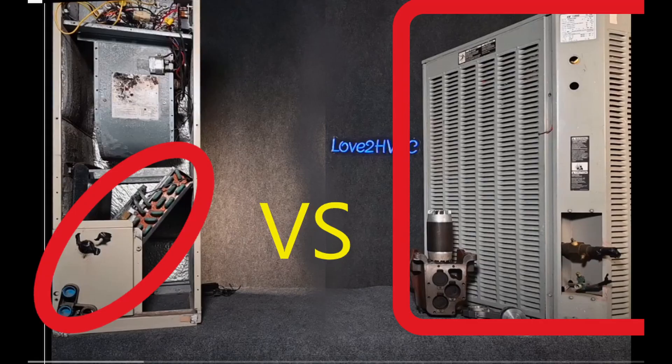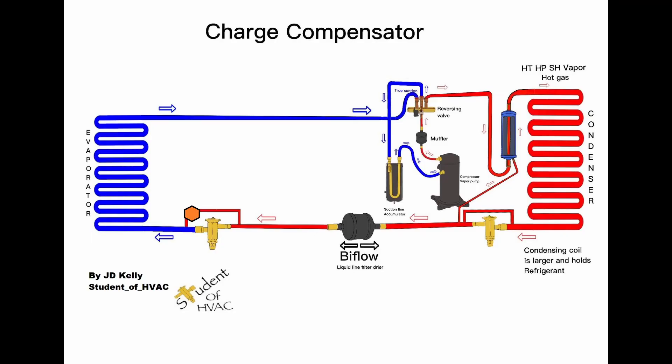That's because the condensing coil was very large in size. It was much larger in volume than the indoor coil and we needed that extra refrigerant to be in the sub-cooling of that outdoor coil.